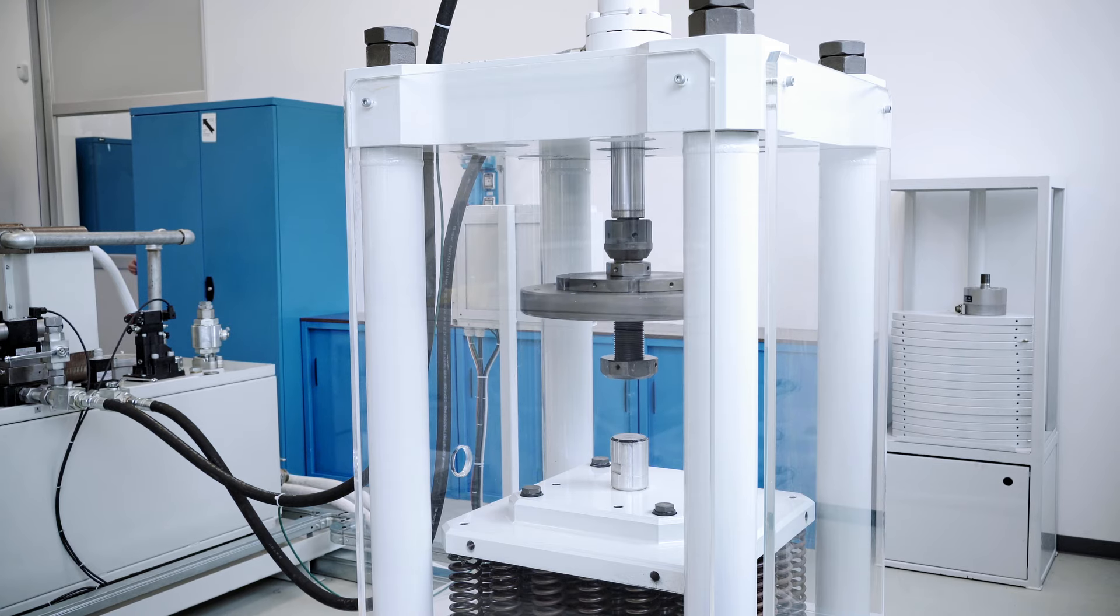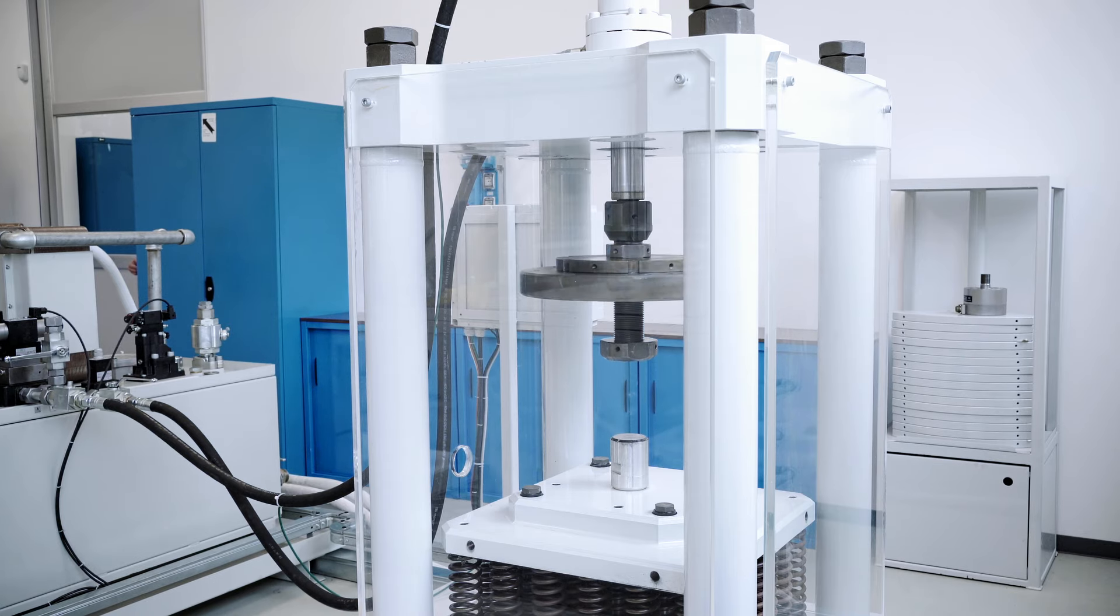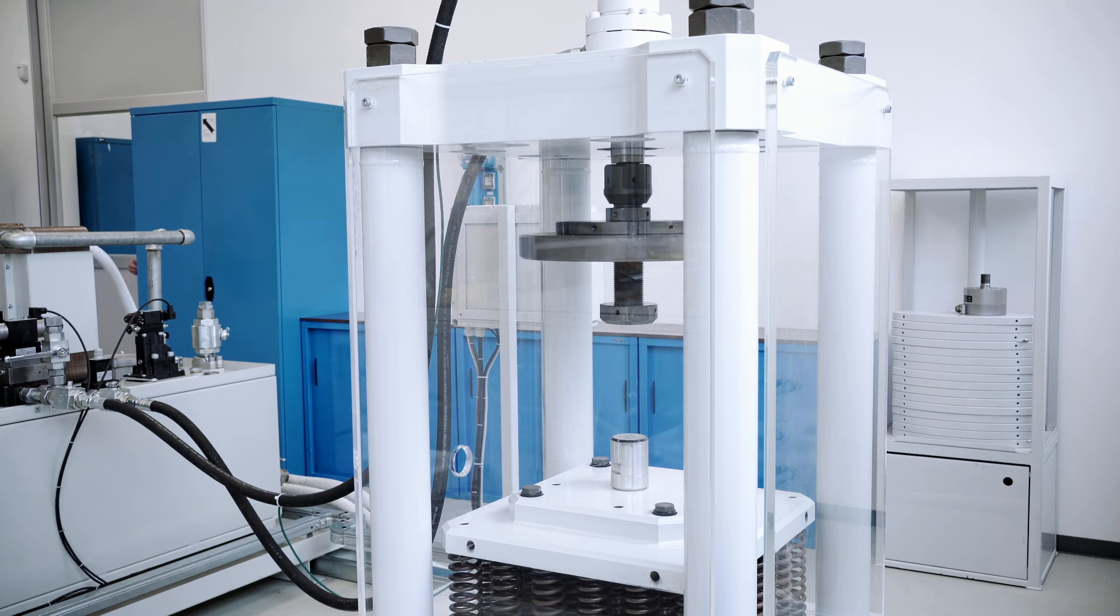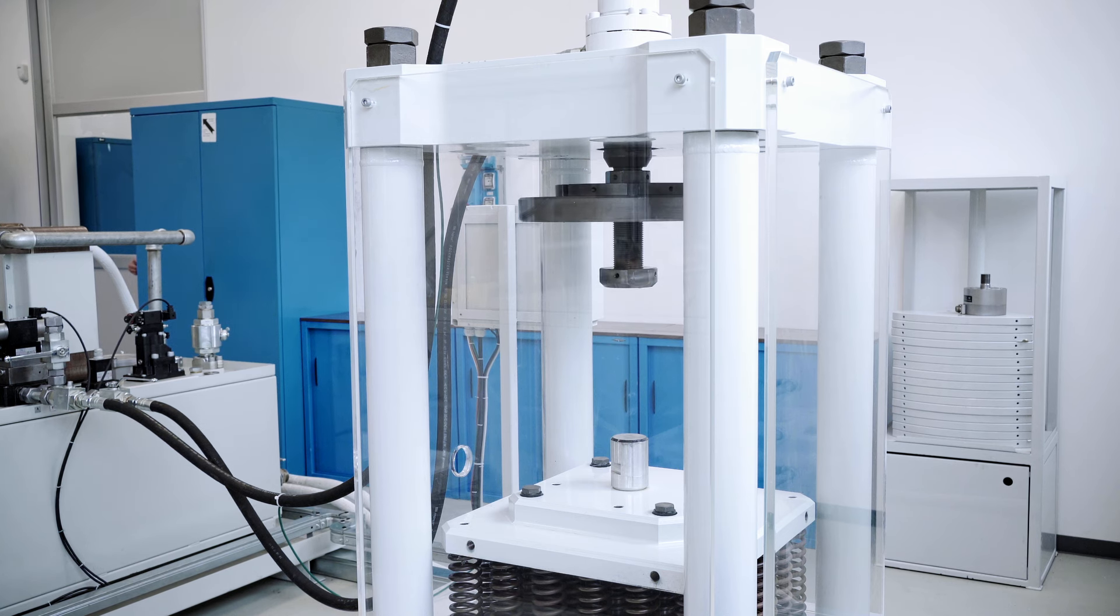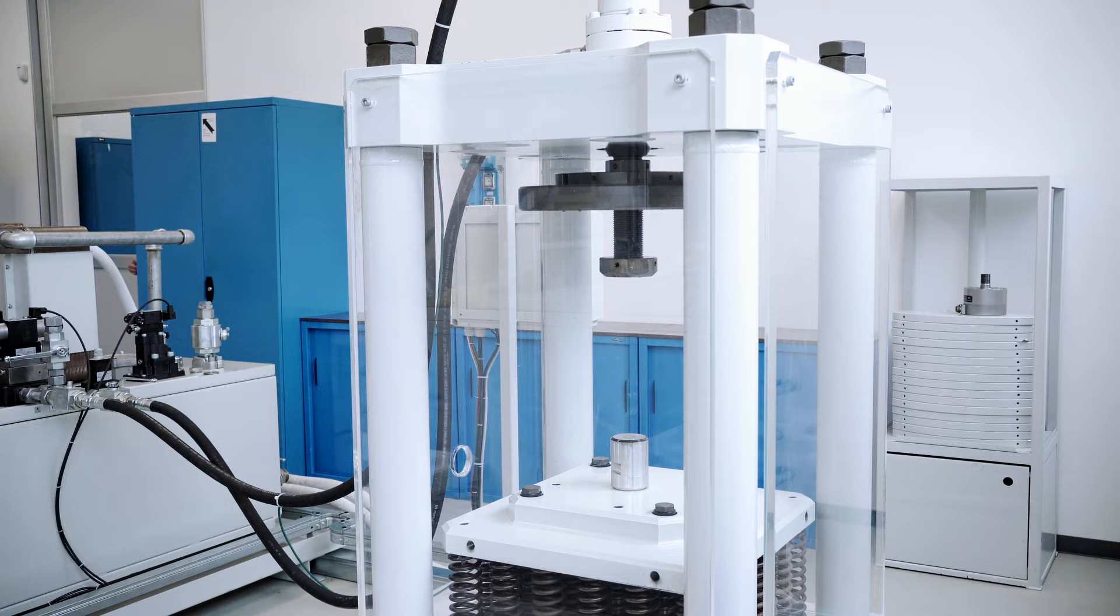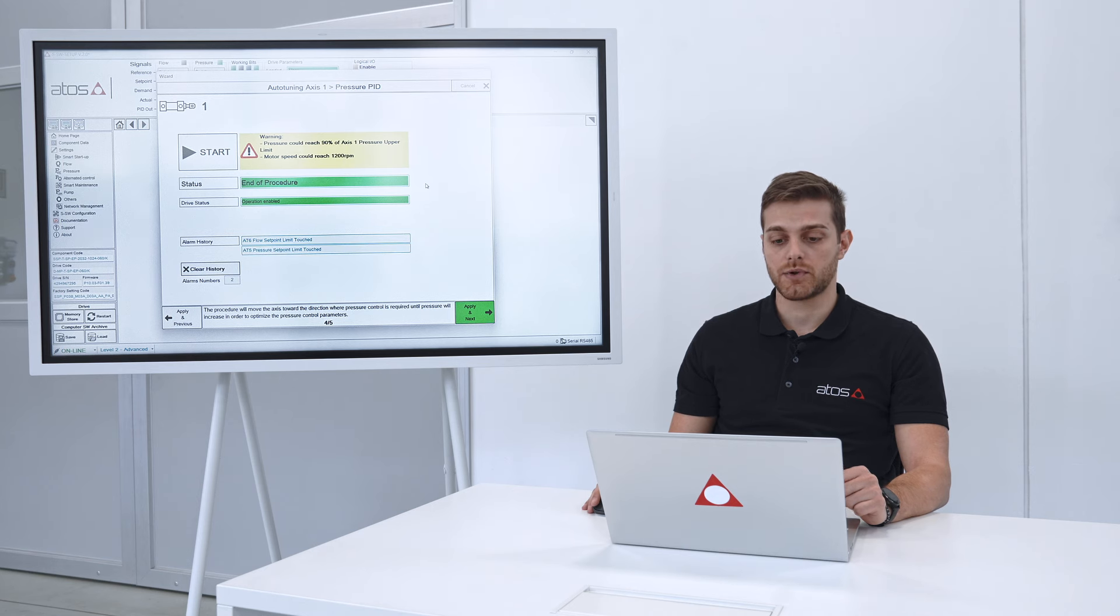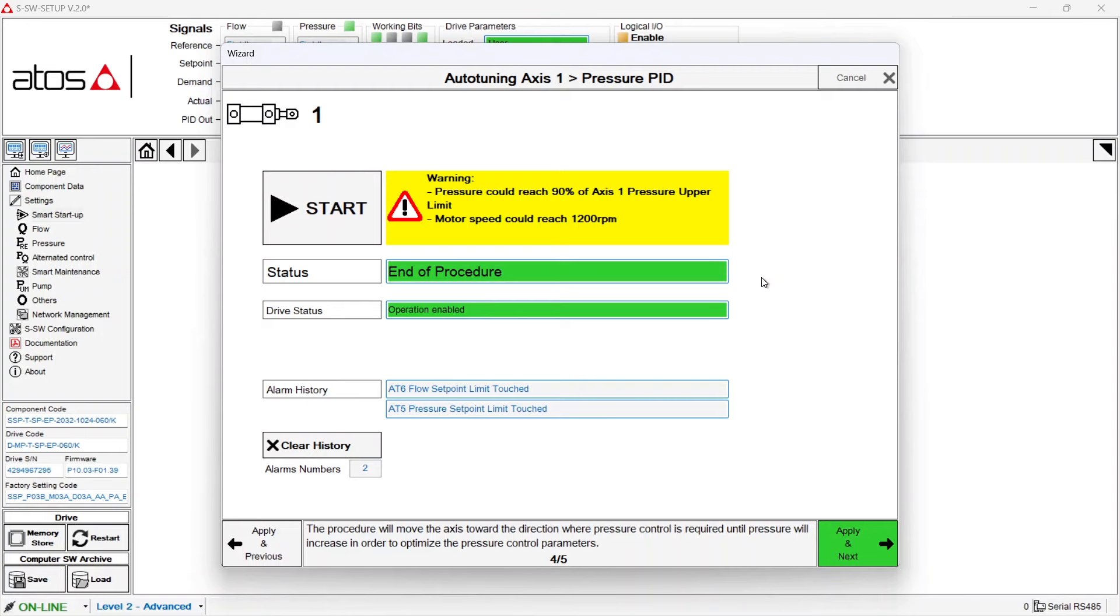The cylinder is moving until it finds a load, in this case the full stroke of the cylinder. And in a few seconds the procedure will estimate the volume of oil inside the hydraulic circuit and will set according to it the optimal pressure PID. The procedure is completed.